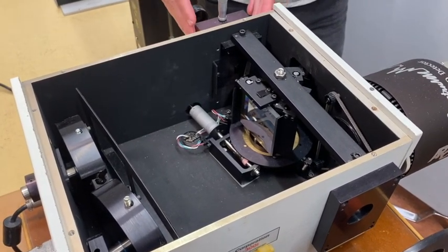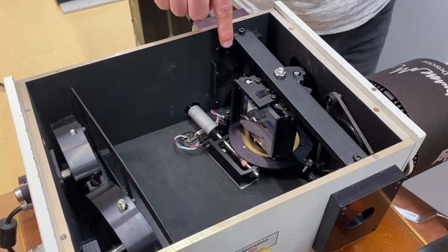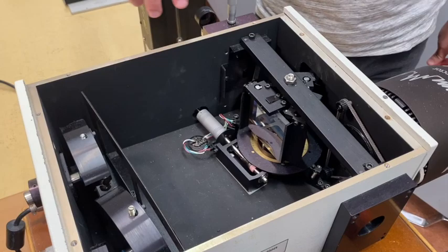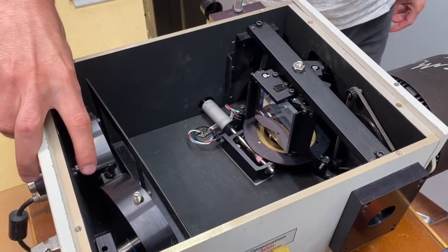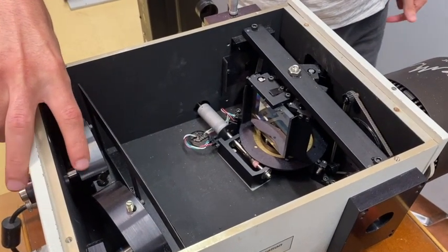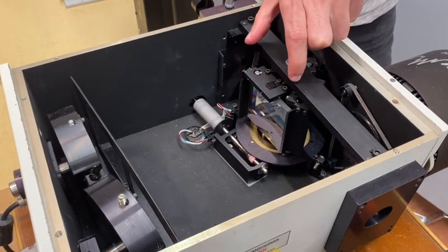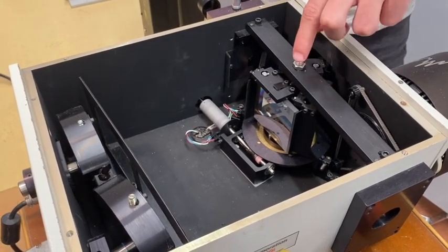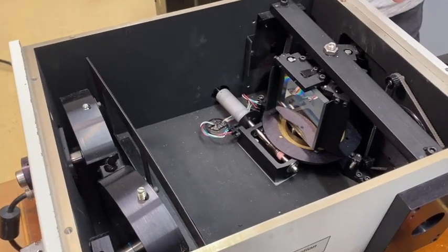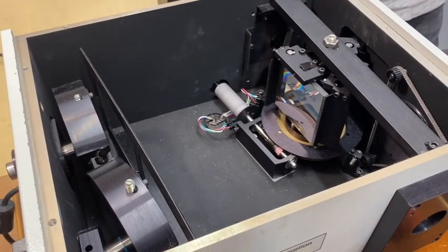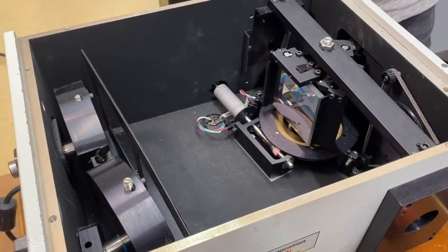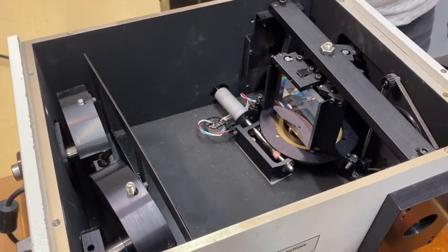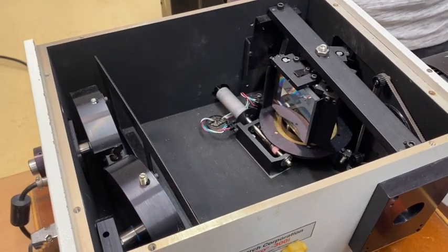Then you have the light transmitted through the slit and reflected by the first mirror inside the box, which will just redirect the light to this mirror, which will reflect the light onto the grating. You have different gratings with different numbers of slits per millimeter. You will work with two of them: one with 300 slits per millimeter and one with 2000 slits per millimeter.